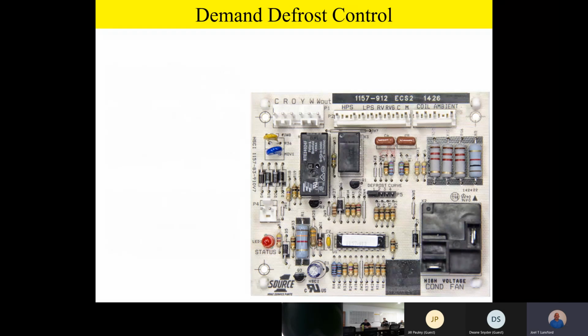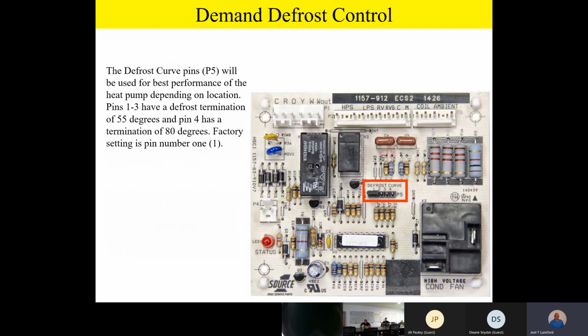All right, team, as we move around the board, we're going to see that we've got a defrost curve jumper. This defrost curve jumper is going to be set on one of those pin numbers based on the tonnage of the unit. Now, it wouldn't be so easy as just 1 ton, 2 ton, 3 ton, 4. That isn't how that works. So basically a 3-ton unit might be on position number 1, a 2-ton unit might be on position number 3. You get the idea. But basically, defrost curve pins are going to be used for best performance of the heat pump depending on your location.